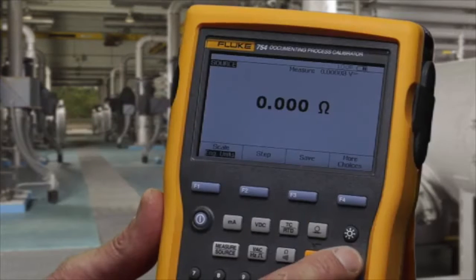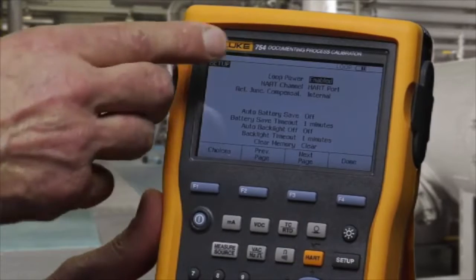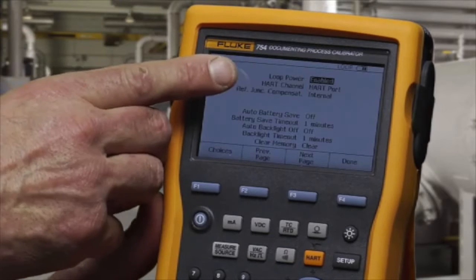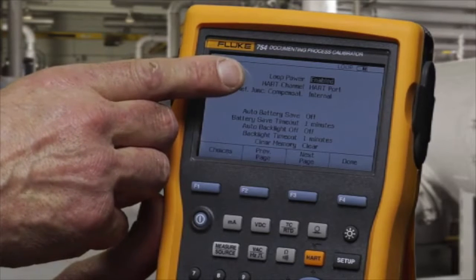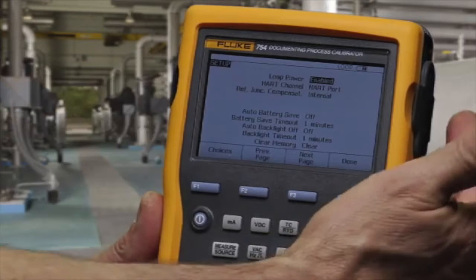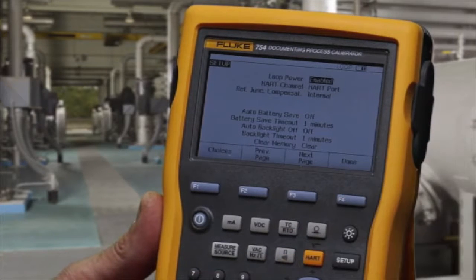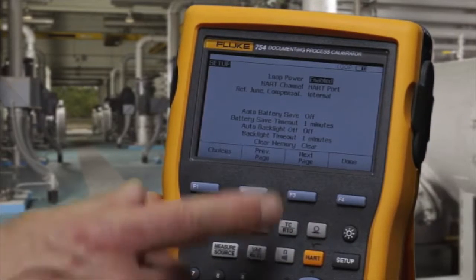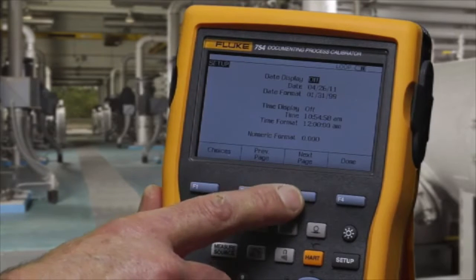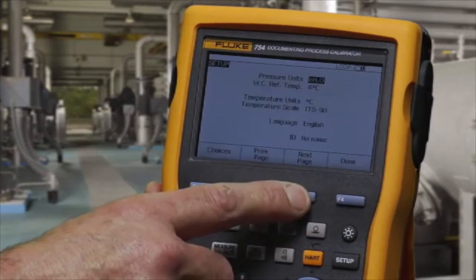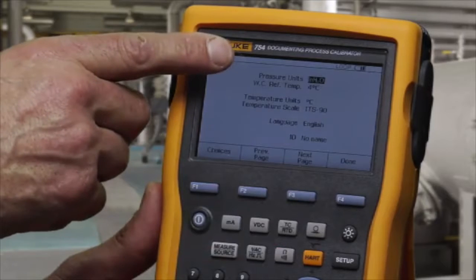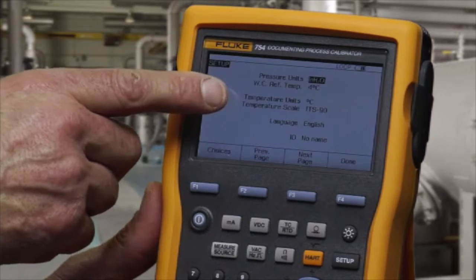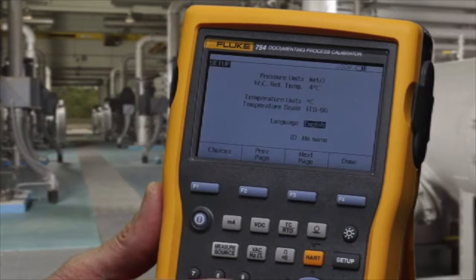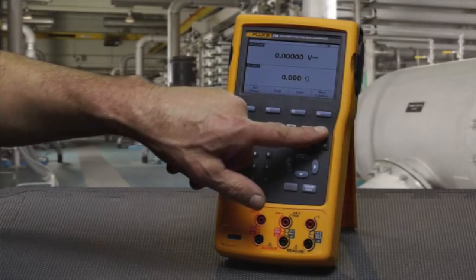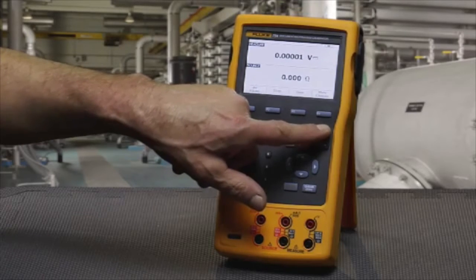In the setup screen, we can configure and turn on loop power. We can change the direction of the HART communication signal from the digital connector on the side to the milliamp measurement ports. We can also set the time and the date. And we can select pressure units, change pressure units, and temperature units, and input our name into the calibrator to personalize it. And the backlight has a low, medium, and high setting.